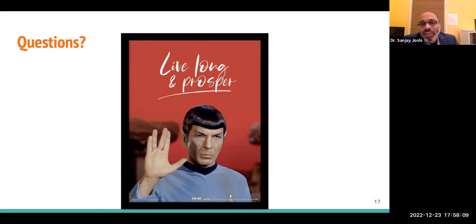But an auditor, if they say, oh, this was the design in, let's say, your discussion number 3, and you figured out it's not going to work, and you came up with a completely different design by your meeting number 4, they would love to see that. And we have actually done it. When we created the robot or the imaging system, everything didn't go right the first time. We iterated through design. We significantly changed the design in order to meet the end user needs. And that absolutely happens. And we do have a record of our failures, the failed design. Again, don't let the standard rule out a photograph, a video, a mock-up. That's good enough. Okay, thanks, Sanjay.